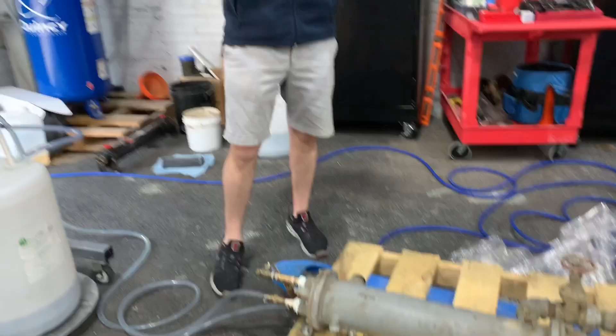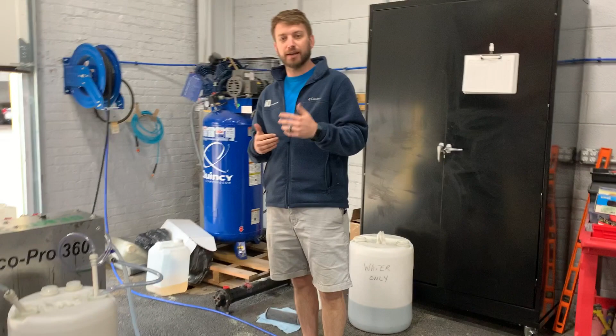This particular one runs oil on the shell side and water on the tube side. Our chemical is 85% water based, so it's not going to come close to cleaning out any oil, which is why I've got these hookups on the tube side here. It loves copper, so a standard heat exchanger takes anywhere from a half hour, and the really bad ones take about 2 hours to flush.